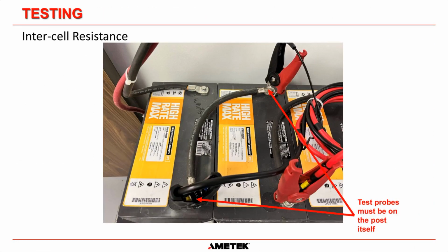So that's the internal resistance that we've been talking about. That's the actual internal resistance of the battery. That's looking inside the battery and trying to see if there's any plate degradation. That is why the internal resistance goes up or the conductance goes down: the plates are starting to sulfate and break down. The other thing that most devices do, especially the Cellcorder, is they test the intercell resistance.